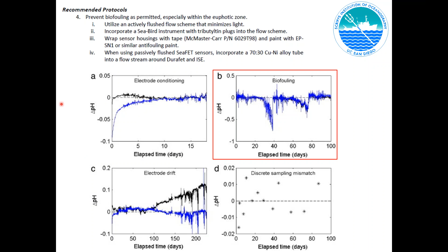This is the same time series of pH anomalies for 4 different sensors located on this mooring. This is in Monterey Bay on a Lobo mooring. And one point to make here is just that we see these decreases in pH due to fouling, and you can demonstrate that this is fouling by going out and cleaning the sensor, and it comes back to the right value. So fouling, cleaning, and some of the implications here are that if you can identify it, you can go out and address the problem depending on how close it is to shore. So in the case of an underway system, we may not have to worry as much, or we may not have to put quite as much effort into thinking up new ways of biofouling prevention, because we can address it by cleaning the system on a regular basis.